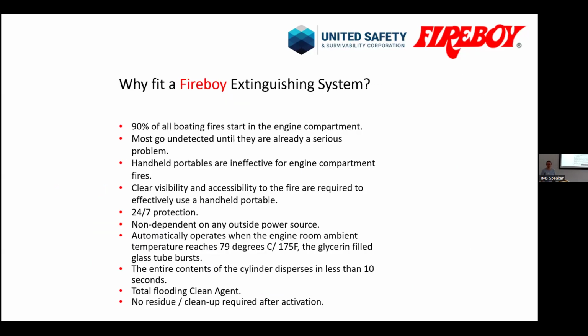So the biggest question is, why fit a fire extinguishing system in a machinery space? Well, 90% of fires start in a machinery space, or these days, in battery or electric rooms, or storage rooms for the diesel or batteries. Most of them go undetected until it's too late. Now, the common thing is, obviously, you always have handheld portables. So the first primary approach would be to try and fight the fire with a handheld, but only if it's safe. Most of the time it has to be a small fire. Do you have a safe exit? That's when the fixed fire suppression comes in. It gives you 24/7 protection with automatic activation.